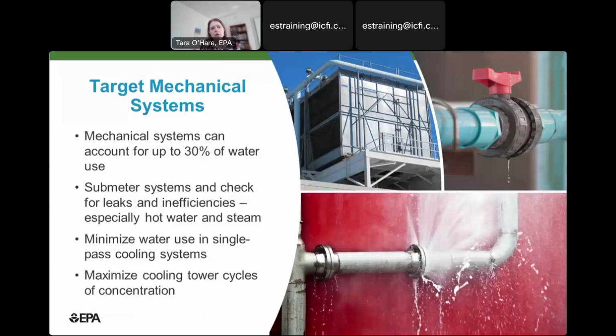So next we're going to talk about mechanical systems a little bit. Mechanical systems can account for 30% of your water use or more, and this is for heating and cooling. So this is a really good system to consider submetering so that you can check it often for leaks and inefficiencies, especially if there's hot water or steam involved. Those can be really important areas of water and energy savings. So some of the main things you can do is minimize the water used in single pass cooling systems, which I'll explain in a minute, and maximize your cooling tower cycles of concentration, which I'll also explain.